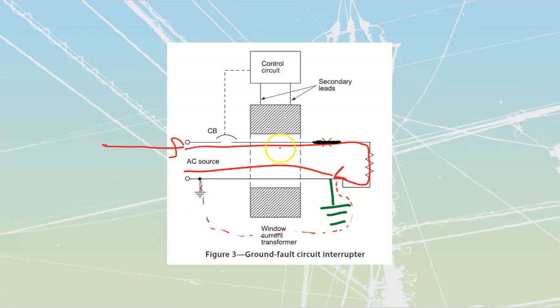And what I see happening at that point is that I've got a difference in current. This might be 12 amps going through here. This might be 11.9 amps. Almost all the same amps, but not quite what we are looking for. As a result of that, we're going to go and operate. Now, how does it operate?